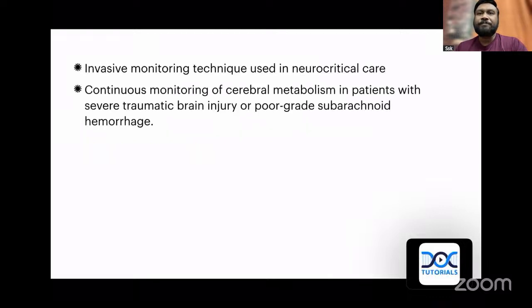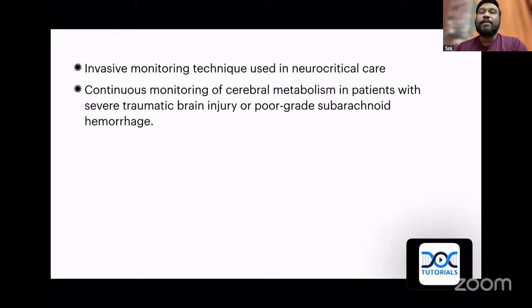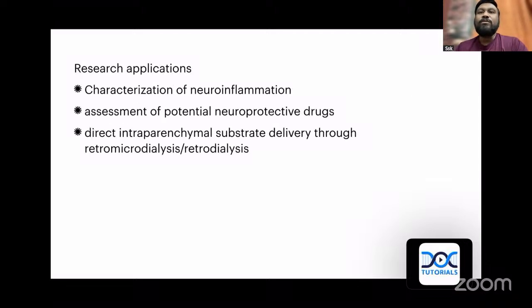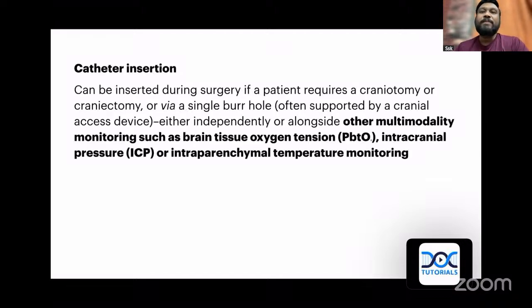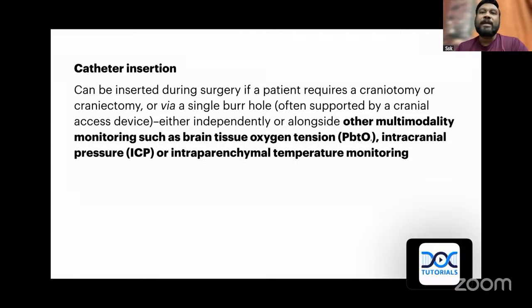Cerebral microdialysis is an invasive technique used in neurocritical care. What we do is continuous monitoring of the cerebral metabolism in patients with severe brain injury or very poor grade subarachnoid hemorrhage following an aneurysmal SAH. They are used in characterizing the level of neuroinflammation, to assess potential neuroprotective drugs, and direct intraparenchymal substrate delivery through retrodialysis. It is basically a catheter inserted into the patient's brain during craniotomy or through a single burr hole. The microdialysis monitor can be used along with other monitors like brain tissue oxygen tension, ICP monitor, or intraparenchymal temperature monitoring.